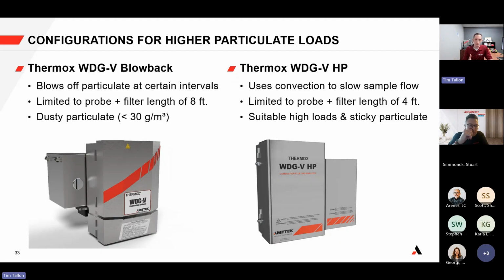But the thing is, with an aspirator, you're pulling that sample through the filter. So over time, that filter will become, I wouldn't say plugged, but it'll start to cake on, and it will have to be cleaned off.